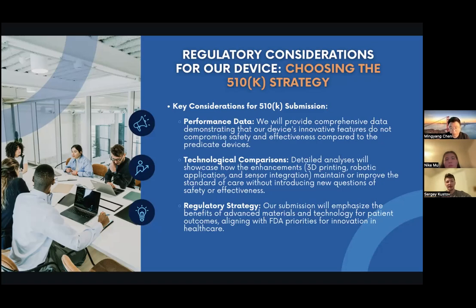So I believe for this portion, choosing a 510(k) strategy. So why are we actually focusing on this strategy? Like I said, compared to the PMA, what we want to showcase as key considerations for 510(k) submission is performance data. We'll be providing comprehensive data demonstrating that our device innovation features do not compromise safety or effectiveness. Those little monitoring structures within the compounded device will showcase how well it works compared to a normal cast.